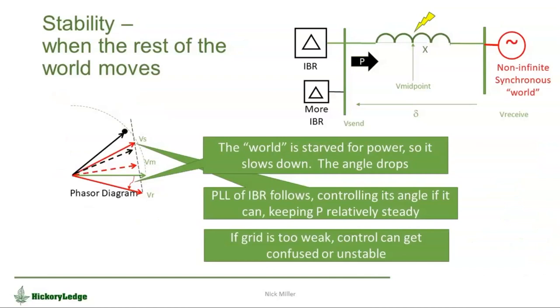So one of the things that becomes rather important here is that the rest of the system actually does move around, and there's no such thing as that infinite sending end, and the system is more complicated. What happens is that everything moves. And the phase lock loop, the control of the inverter-based resource, tries to keep up and tries to keep P, the black arrow, more or less fixed, unless it's got some other instruction. So the sending end phasor will chase the receiving end phasor in a fashion that keeps the behavior that you saw in the previous slides more or less the same. It's not like it's truly just sitting there. That doesn't happen. That becomes important now when we go to worrying about weak grid.